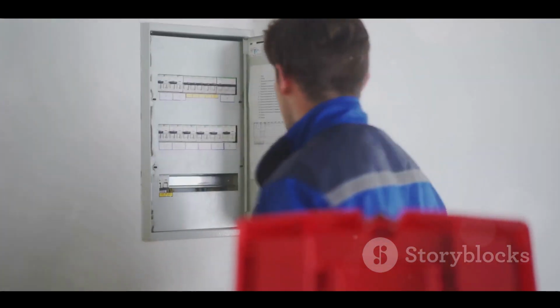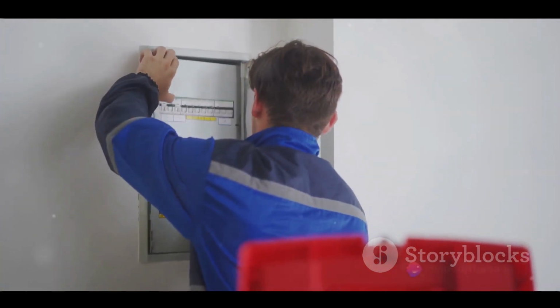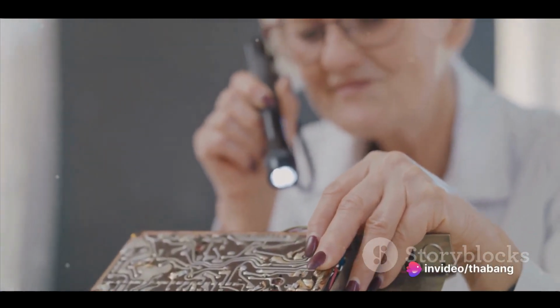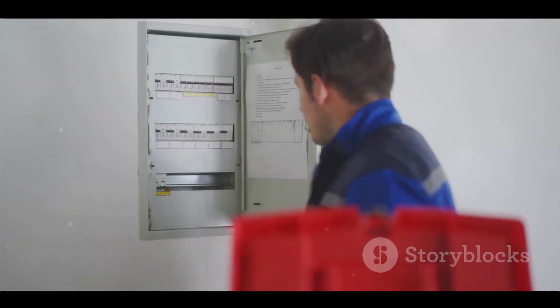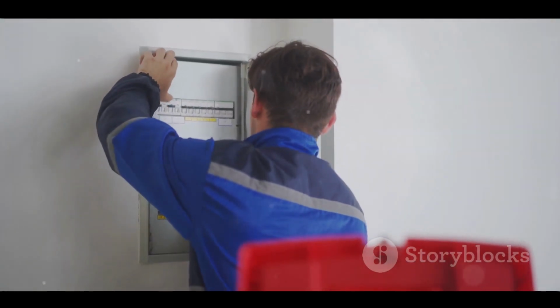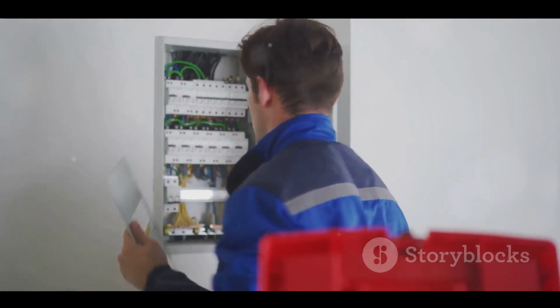The third step involves pushing up the circuit breakers one at a time. As you do this, keep an eye on the earth leakage breaker. If it trips, you found the culprit, this is the breaker causing the leakage. Once you've identified the offending breaker, leave it in its tripped state, then reset the earth leakage breaker again.